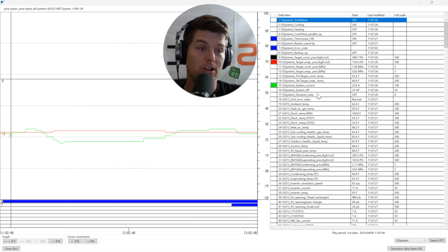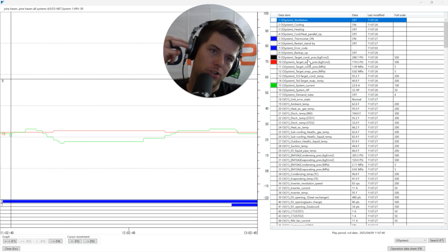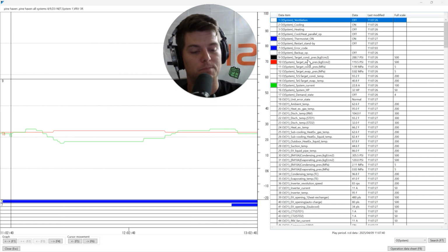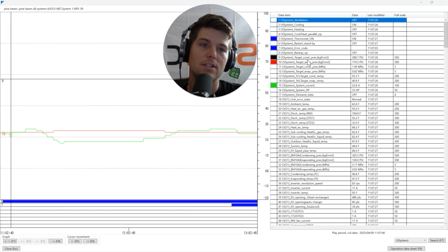So this data set was really great because, again, you don't see many like it. This is a triple module, right? This is my gang sign today. VRV3 triple module system, heat recovery. And we have an issue where he's lost multiple compressors on this system, has not been able to pinpoint the exact cause of the failure, which happens. For this specific instance, he knows he has low discharge superheat, extremely low discharge superheat, and also low suction superheat. He just can't find the floodback.